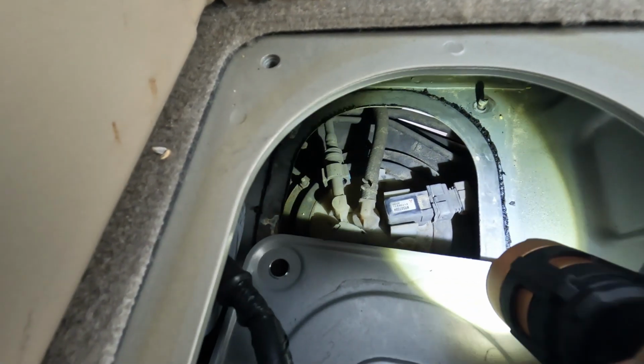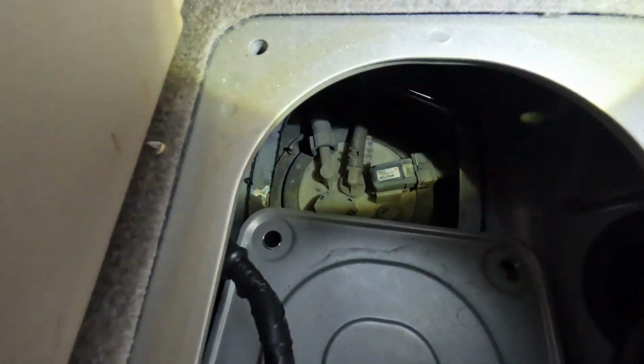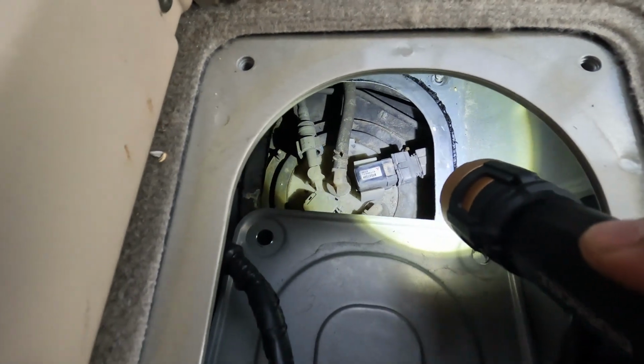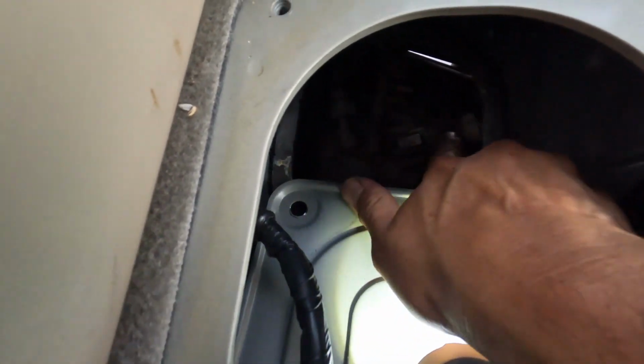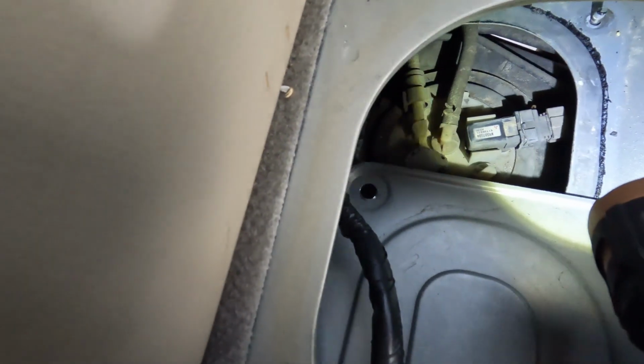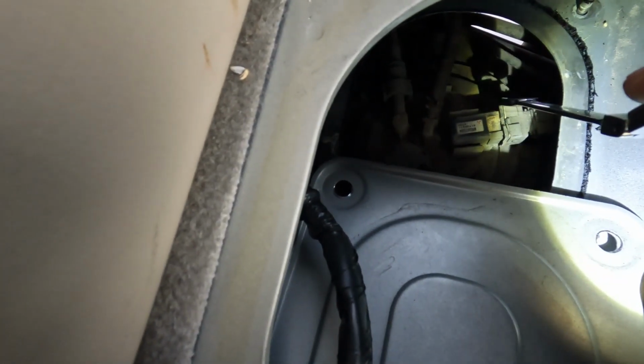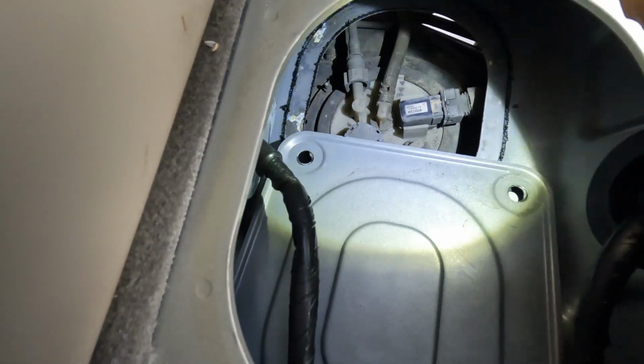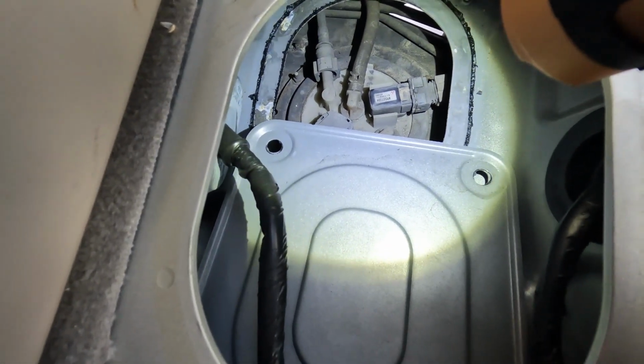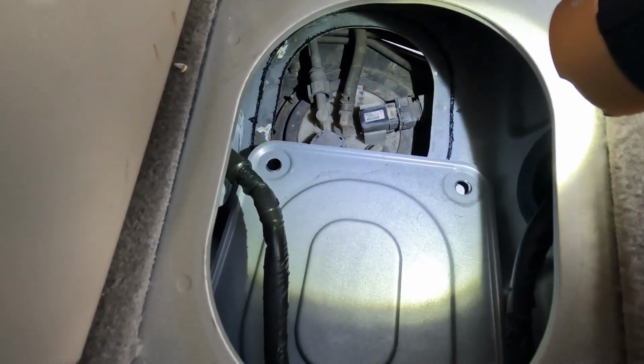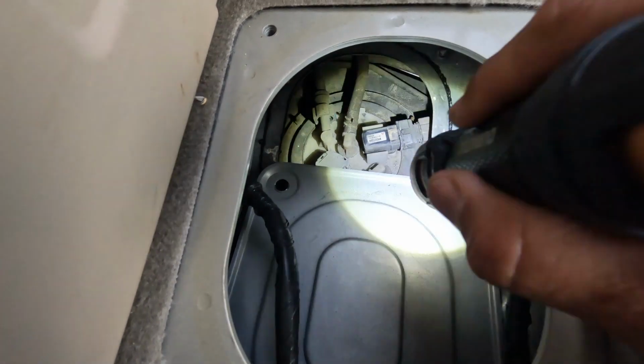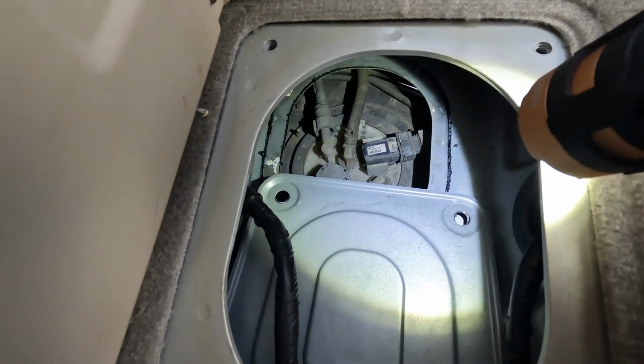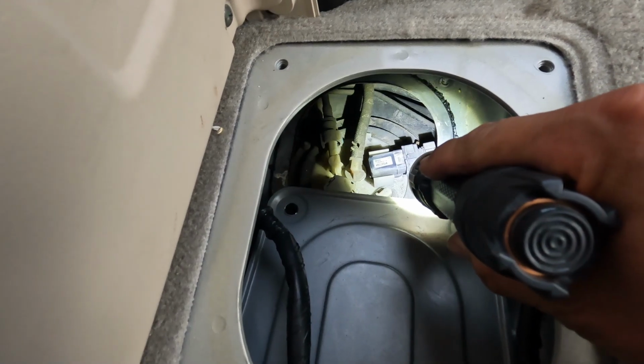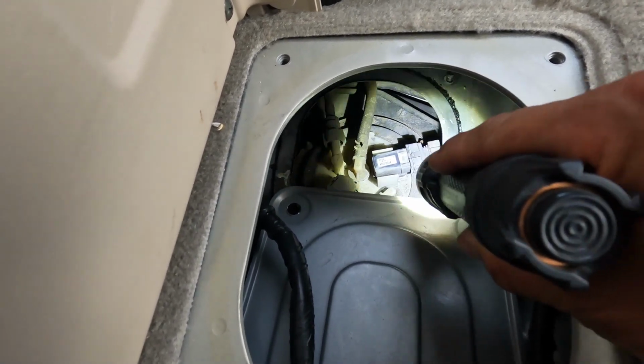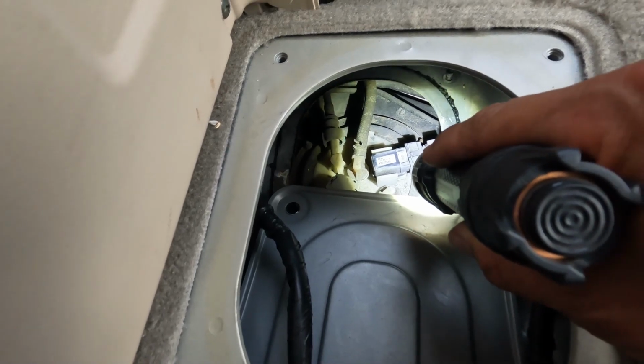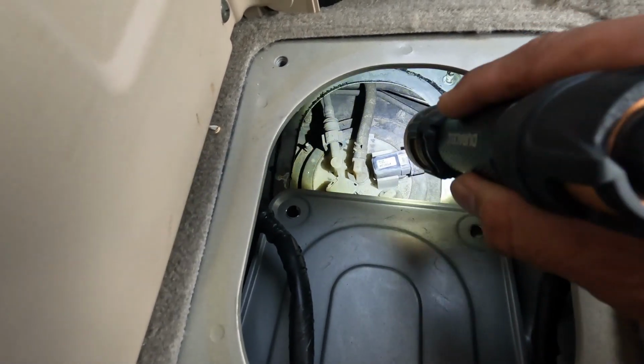Okay, so you can see the pump connector. I believe this connector you see right there is the connector at the pump, F07, according to the wiring diagram. So if it comes down to it, I know it's a pain to get down here, but we would have to go disconnect that and see if we're getting power to the terminal coming from terminal number 3 of relay number 2 down to this area.